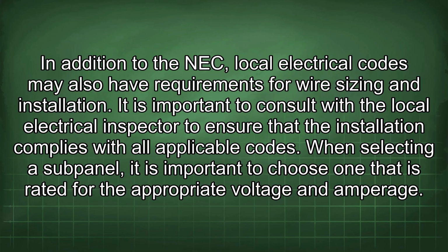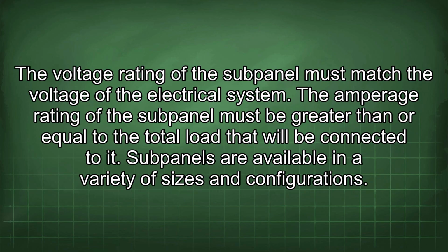In addition to the NEC, local electrical codes may also have requirements for wire sizing and installation. It is important to consult with the local electrical inspector to ensure that the installation complies with all applicable codes. When selecting a subpanel, it is important to choose one that is rated for the appropriate voltage and amperage. The voltage rating of the subpanel must match the voltage of the electrical system. The amperage rating of the subpanel must be greater than or equal to the total load that will be connected to it. Subpanels are available in a variety of sizes and configurations.